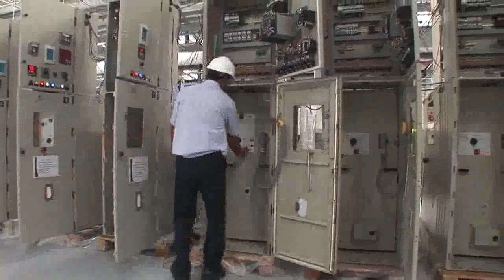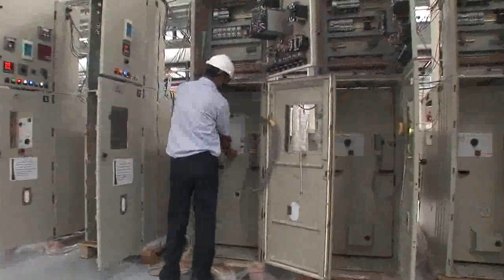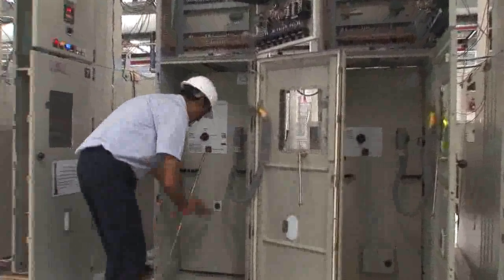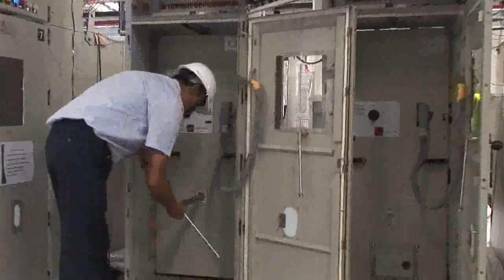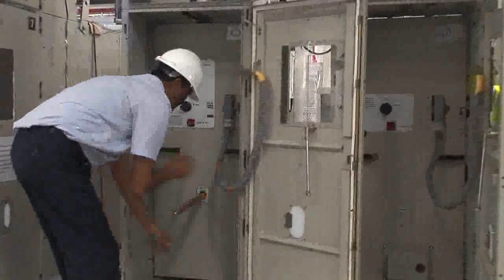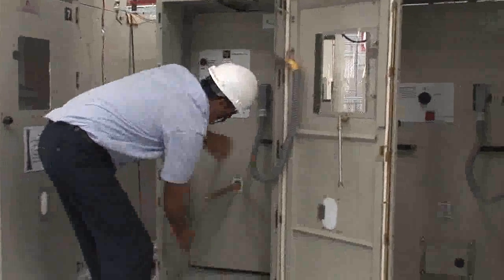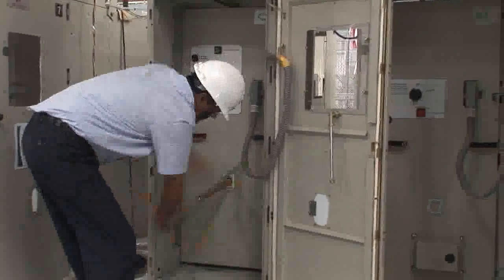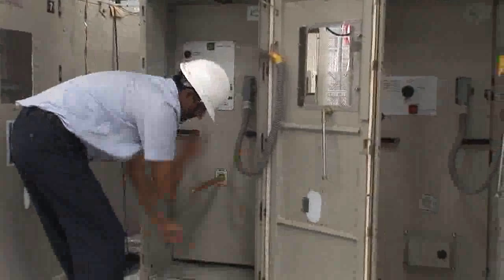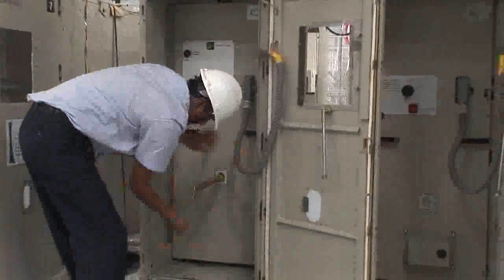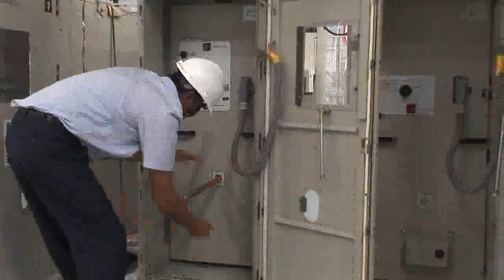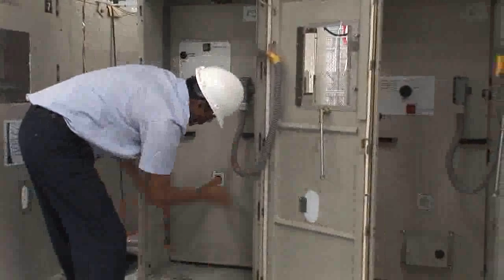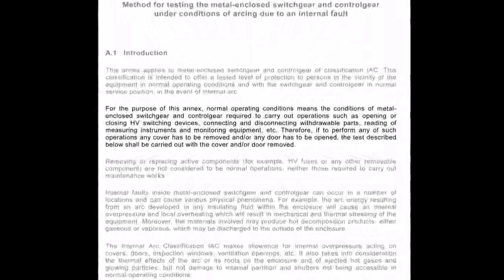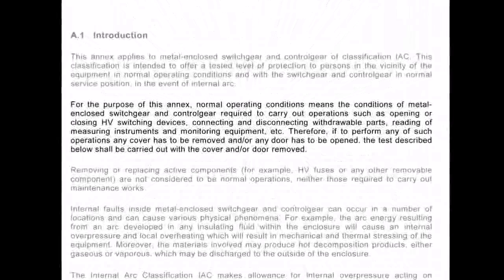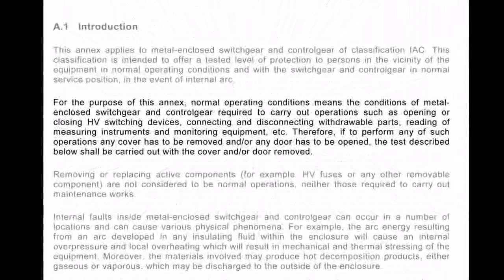What advantage could a successful withstand of this internal arc test possibly offer if the front door of the cubicle is kept open during the operation of the switchgear? This brings us to another example, which comes from the fact that the old IEC did not demand that switchgears be tested in real working conditions, whereas the new IEC makes it mandatory to simulate the real operating conditions as much as possible.